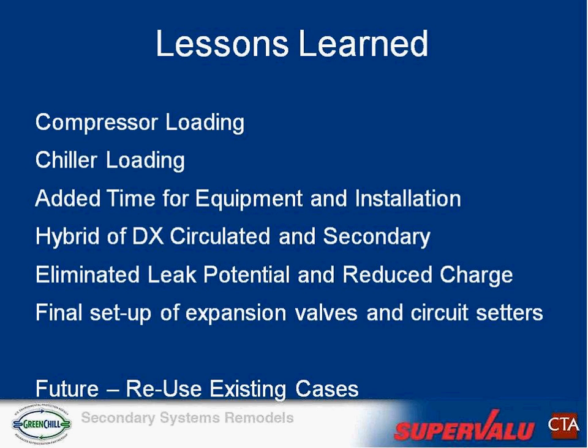Both stores we converted from R22 to R404. So we had to replace the gaskets in those, because they would have just leaked like a sieve when you remove the R22 - the gaskets would have shrunk and we would have had a leaking system. So it's one of the lessons learned: even though we're using existing compressors, we needed to spend a little time doing some additional gasket changes and stuff like that to make the systems tighter.